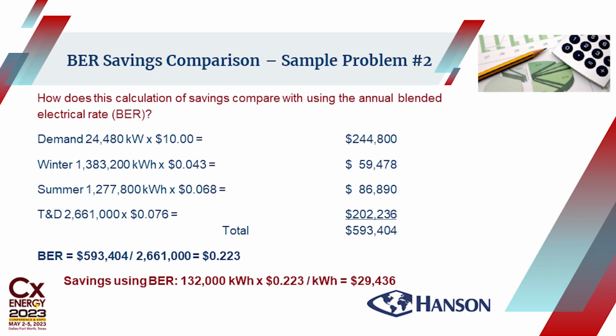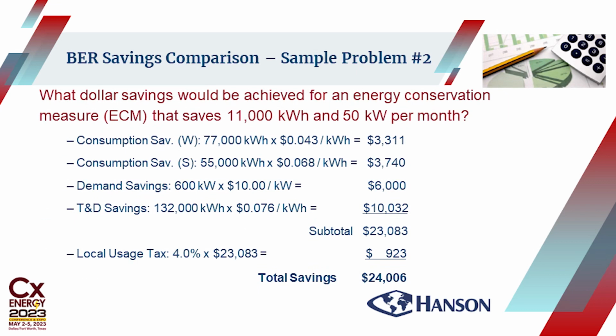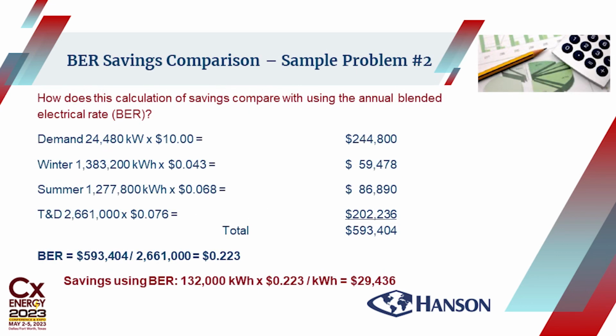So if we take the blended electrical rate times our projected savings from the last slide, and I think my batteries went out. Go back one. Okay. We said 24,000. Go up one again. 29,000. So you see, the blended electrical rate here would give you an estimated savings $5,000 more than if we had done it in the increments that we did. So my only thing here is a cautionary tale: be very careful if you start doing that, because of the new rate structures, and depending on what your measures are.